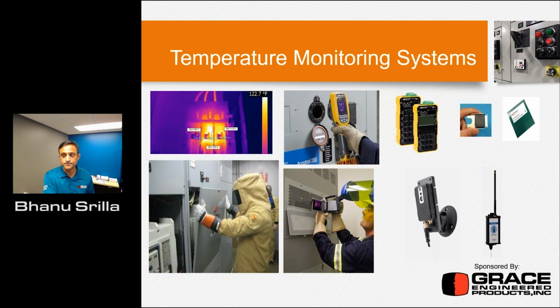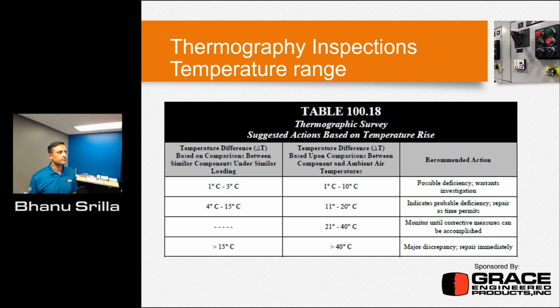That's pretty important. So this is the next slide, thermography inspections temperature range, because most people ask, what is this reference point? This is taken out from ANSI/NETA MTS-2019. So as you look at it, anywhere there's a temperature of 1 degree to 10 degrees C, that shows a possible deficiency warrants investigation, meaning you do this inspections, right?